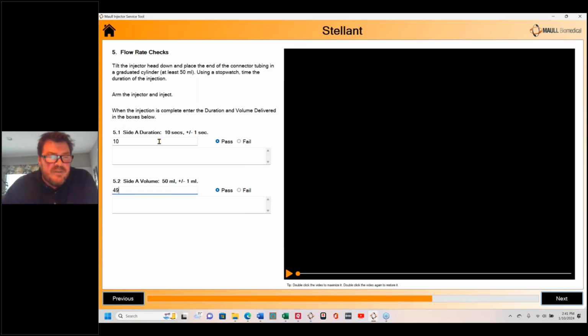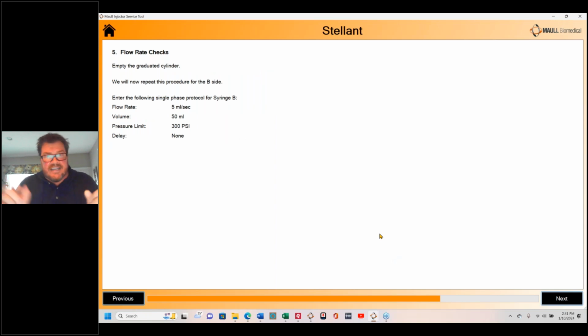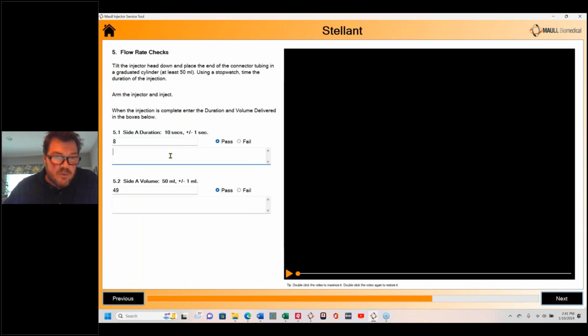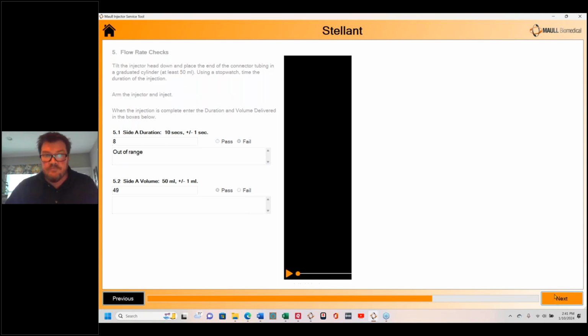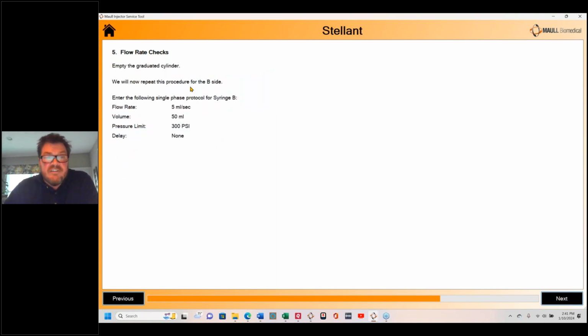Now, one thing I did not do with this software: if I put 8 seconds here, when it's 10 seconds plus or minus 1 second, and say pass, I didn't set the software up to flag that. I just left that to the BMET. So if I click next, it accepts it. It doesn't flag and say, hey, that's out. I pondered that, but I thought, nah, the BMETs know what they're doing. If it were out of range, that's what the notes section would be for. And obviously something like that, we would put fail. All right, and then this is just saying repeat everything we did for the B side.